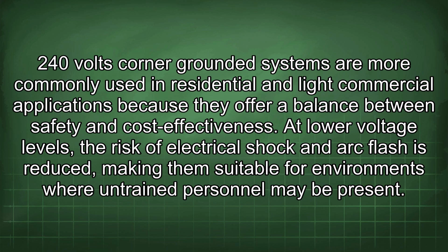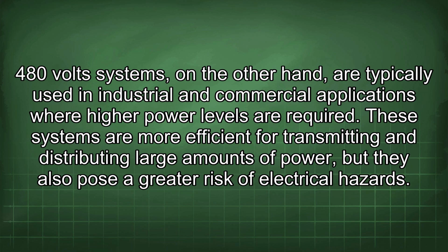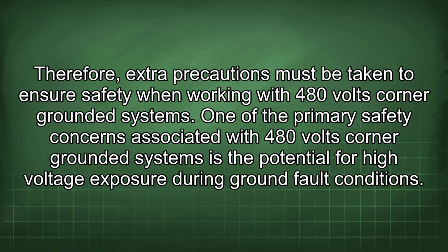240 volts corner-grounded systems are more commonly used in residential and light commercial applications because they offer a balance between safety and cost-effectiveness. At lower voltage levels, the risk of electrical shock and arc flash is reduced, making them suitable for environments where untrained personnel may be present. 480 volt systems, on the other hand, are typically used in industrial and commercial applications where high power levels are required. These systems are more efficient for transmitting and distributing large amounts of power, but they also pose a greater risk of electrical hazards. Therefore, extra precautions must be taken to ensure safety when working with 480 volts corner-grounded systems.